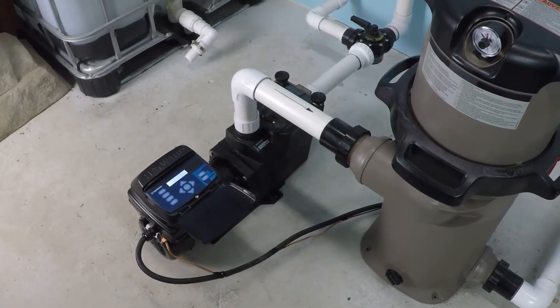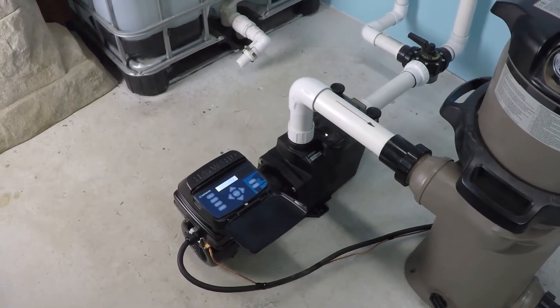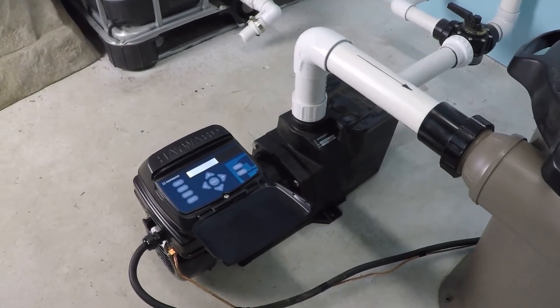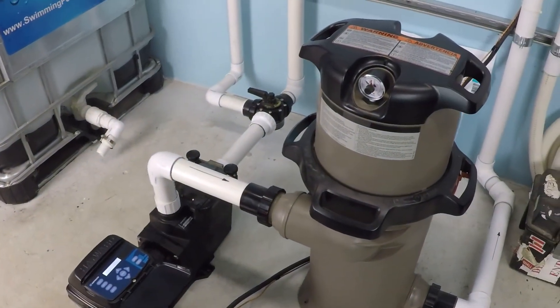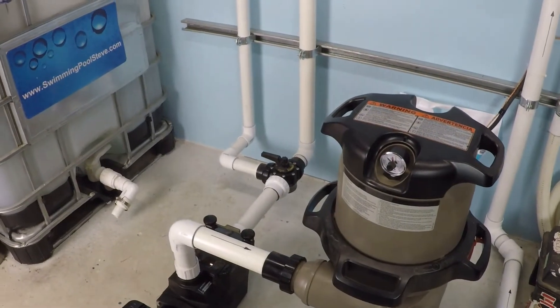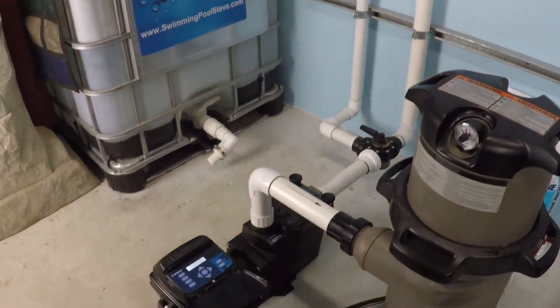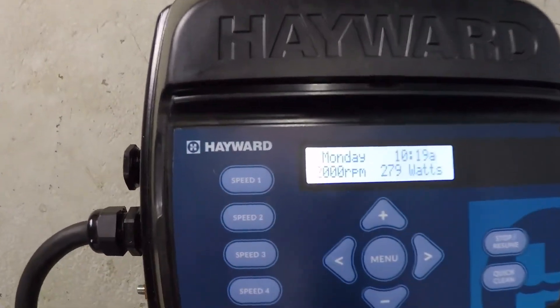In this video we're going to be looking at the flow rate of 40 gallons per minute with this Hayward Super Pump variable speed swimming pool pump, which is installed with 230 volts as the electrical service, going through a 150 square foot cartridge filter. Both the suction and discharge lines are one and a half inch — a single one and a half inch pipe.